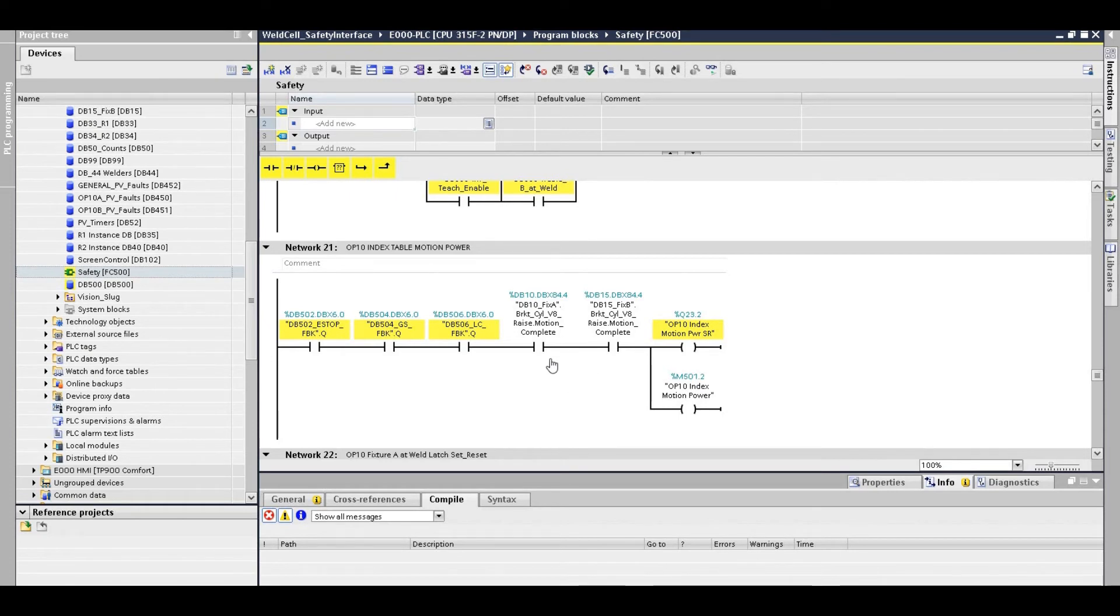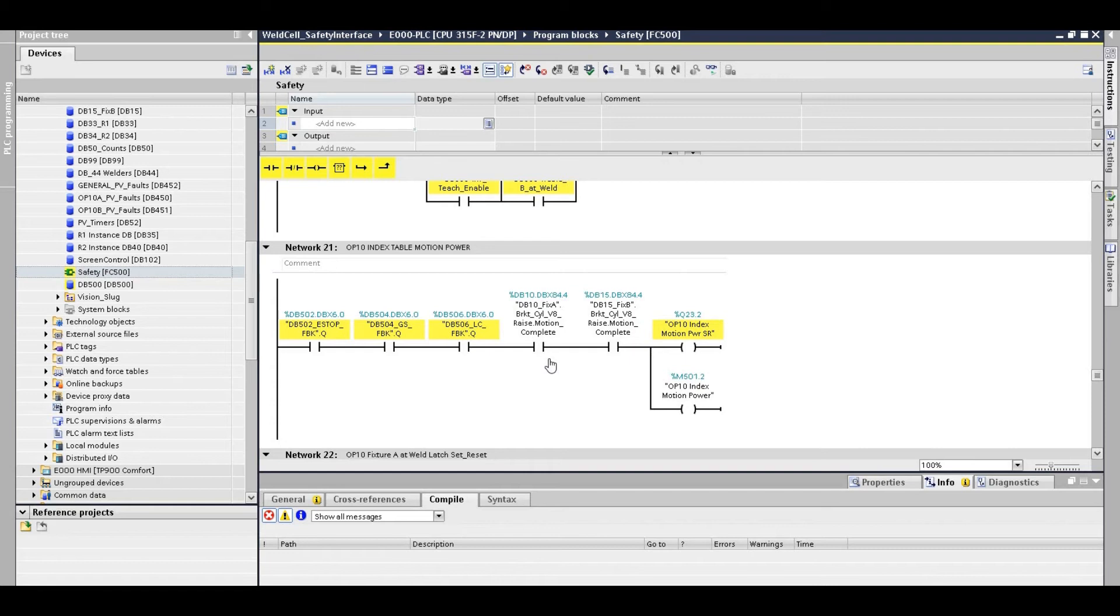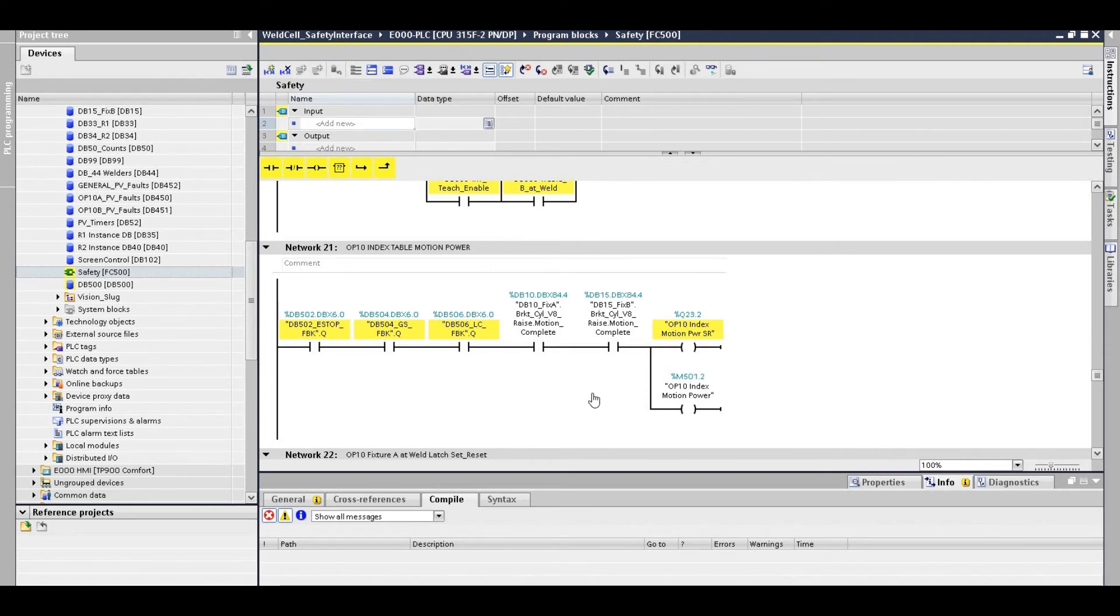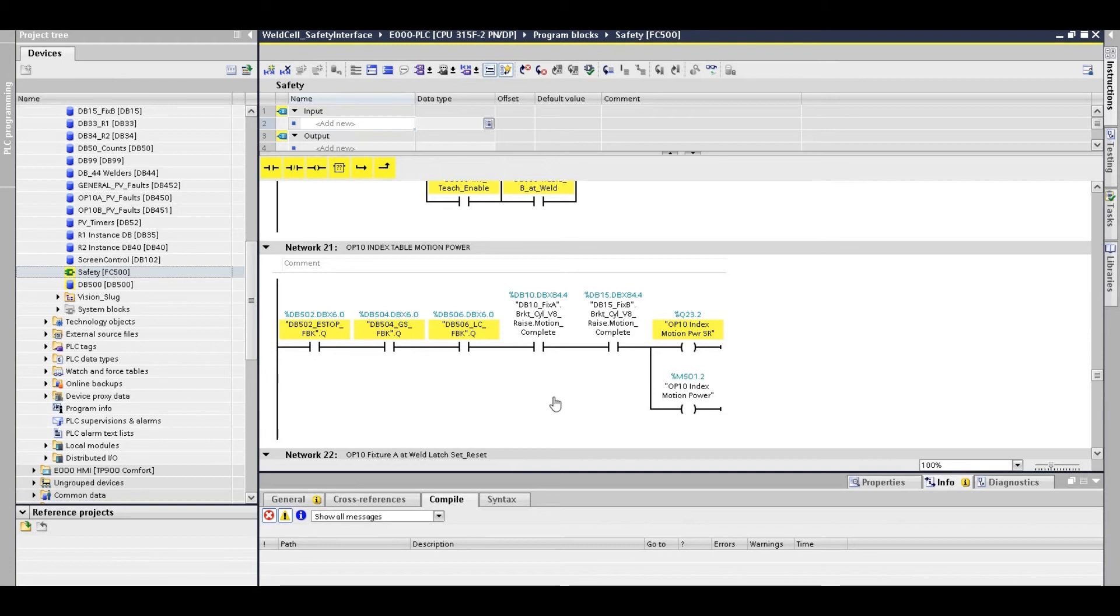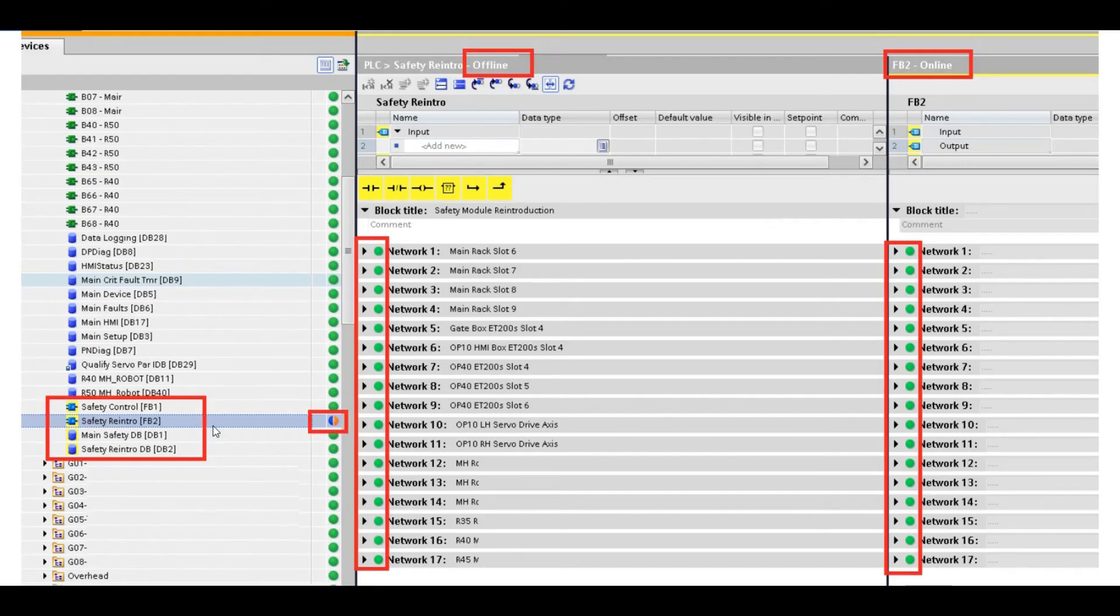At that time, I didn't open the safety logic. I didn't know the safety logic used these two DBs. There's the inevitable change or add something in this existing DB. After the DB10 and the DB15 got changed, after we compile this controller and download the standard FC and DB, the safety found the difference because that DB recompiled and the timestamp got changed.